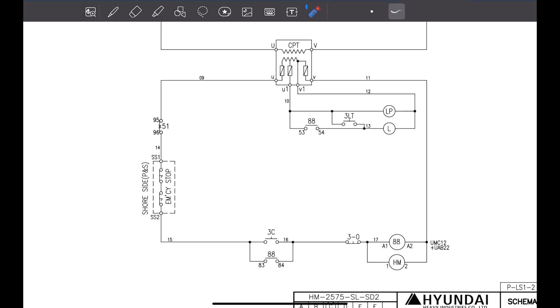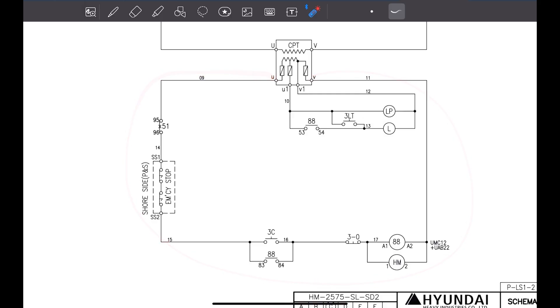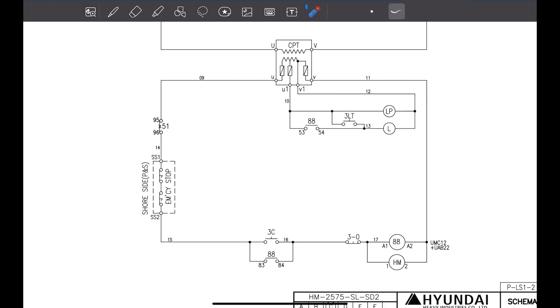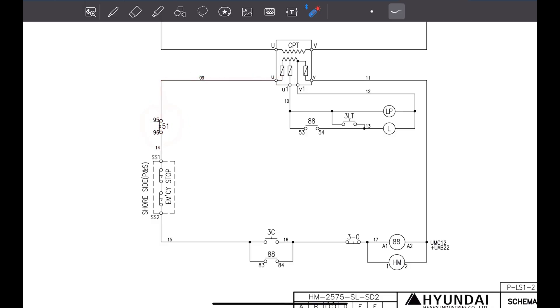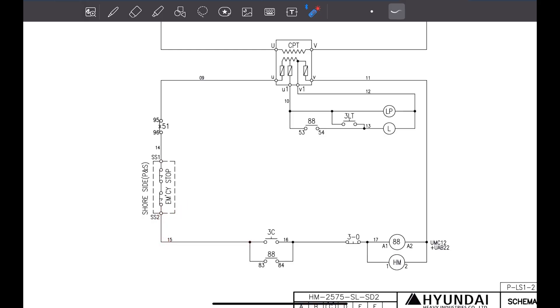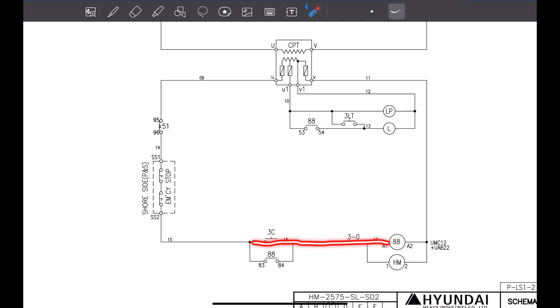Now, you see how this control circuit is working. See the power is coming. The transformer is stepping down the voltage. Now, it is coming from here. This is a closed circuit 51. This is the overload current protection. This is closed circuit coming here. See all these are closed. This is emergency stop. Close close here. It comes here. Now, the circuit is not completed here because this is the open part. This is the press button 3C. If you press this it will start here. The circuit will get completed and it will come here and 88. 88 will get energized.